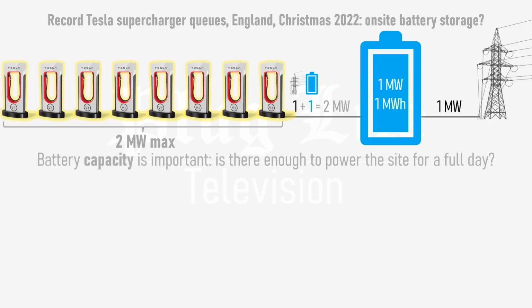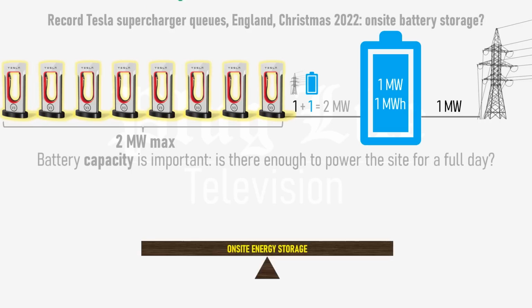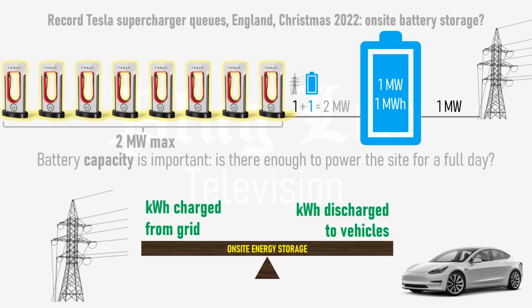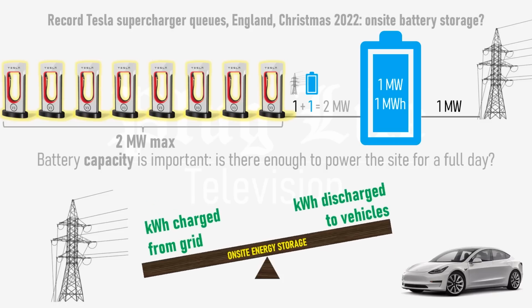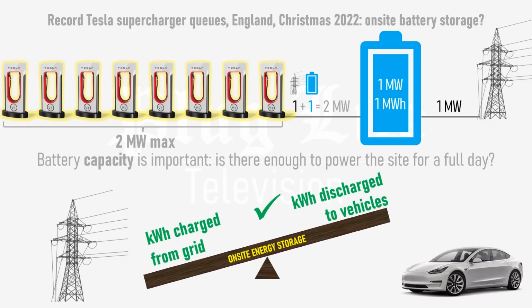Battery capacity is also important. The battery needs to be able to store enough energy to power all of the chargers for a full 24-hour period. If the total energy in kilowatt hours discharged from the battery to cars using the superchargers is less than the total energy charged from the grid by the battery over a 24-hour period, then a battery will work very well at the charging hub.